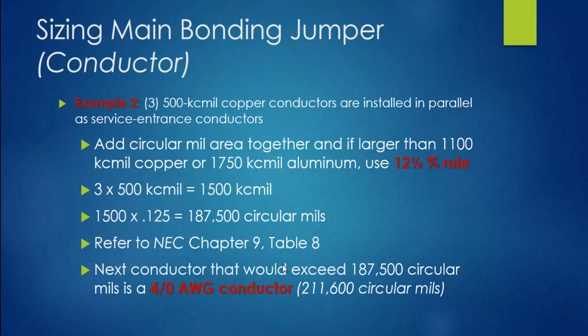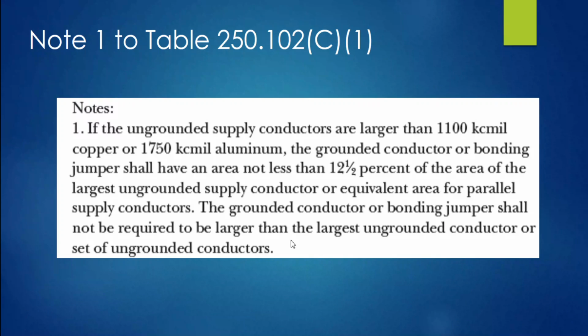All right. Now, let's talk about those notes for a second. We just said it, and I wanted to remind you again, if it's over 1100 copper or 1750 aluminum, then the grounded conductor or the bonding jumper shall have an area not less than 12.5%. So that's where we get the 12.5%. Okay. I will remind you that it also tells you that the grounded conductor or the bonding jumper shall not be required to be larger than the largest ungrounded conductor or set of ungrounded conductors.